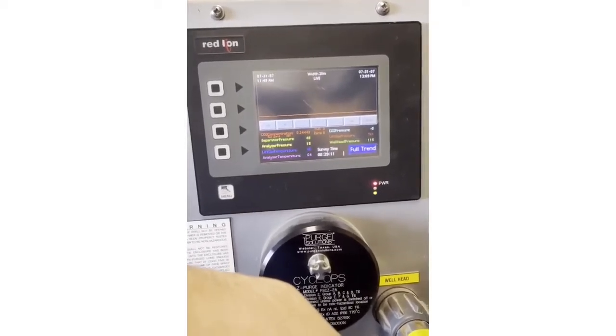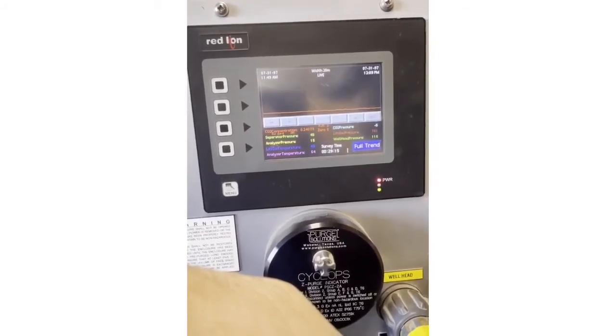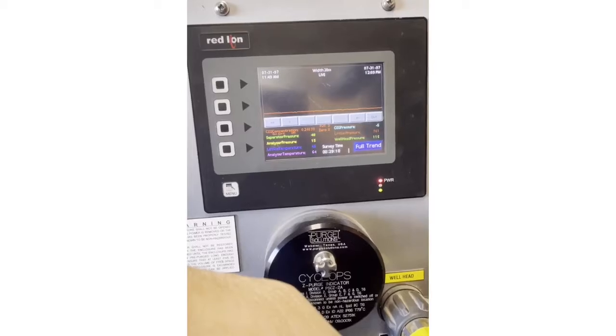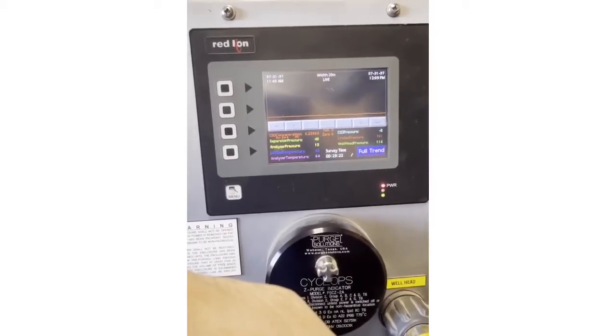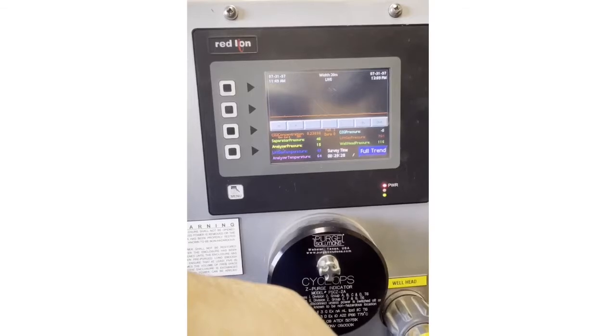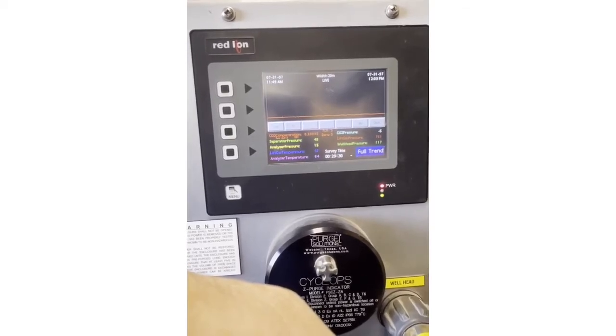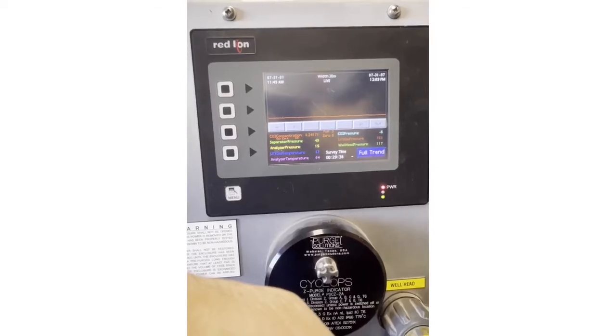It could be many things. It could be a valve is an issue. It could be plugged open. It could be washed. Sometimes we will actually identify that their metering is actually off quite a bit, and we have to readjust our program or our survey when we get proper test data for flows and that. So we do see that a lot.